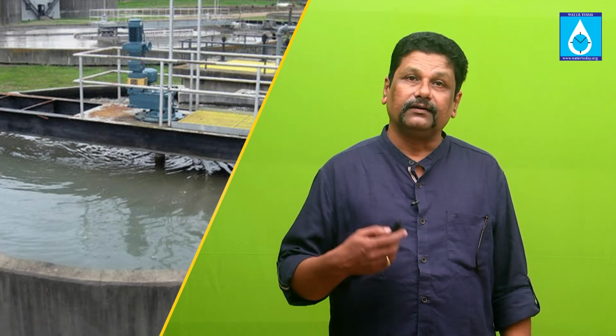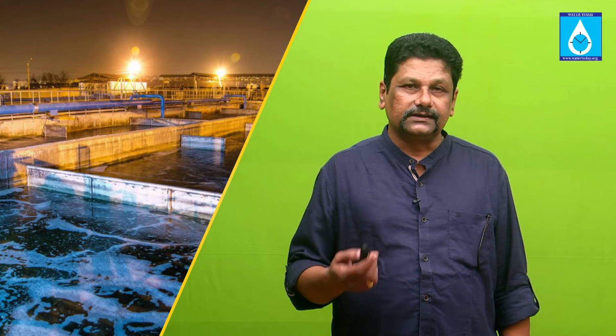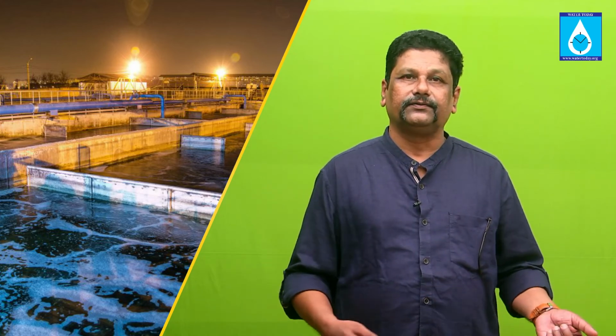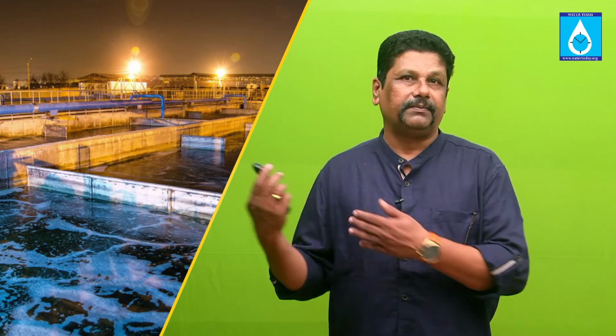Only that we need to go through it ritually and decide what kind of automation I need. And the level of automation is very important. Some of the things which you won't use at all, please don't do it. But what I need is important, please do it. And that is how you can save the pumps. You can schedule your maintenance. You can see alarms. So everything can be done once you have this communication. And sometimes I also advise you can put a submersible mixer into it, and the mixer starts before the pump starts, so that all the sludge and everything is suspended, and it is easy for the pump to take it and pump it out.